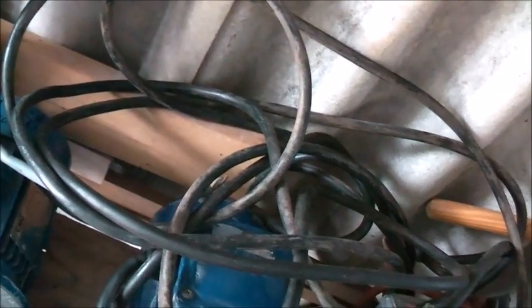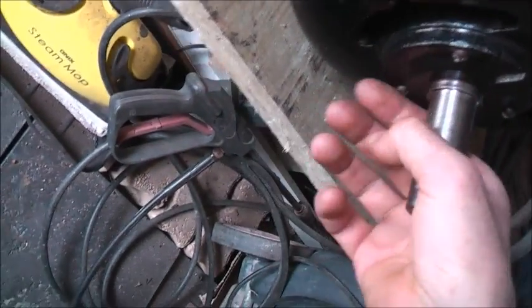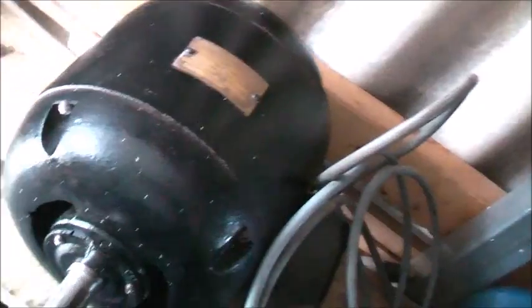There's one set in this that was good - the front one on this one and the back one on this one. The front one on this one was good, but the back bearing on that one here is noisy as well. So this is going to need a bearing in the back. It's always noisy bearings I can't fix - almost always a back one in my case. So I'll put that back in storage and give it a really good clean with compressed air.